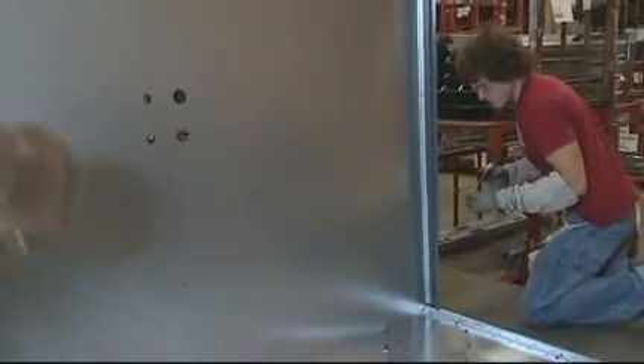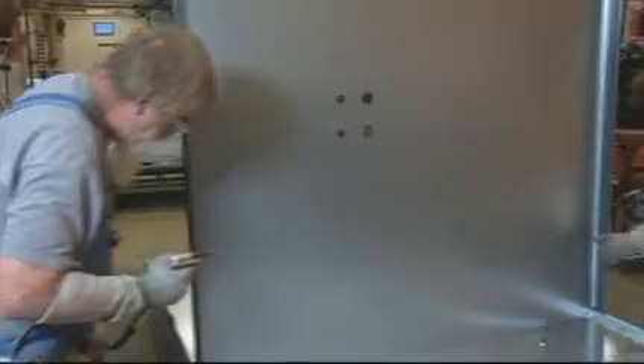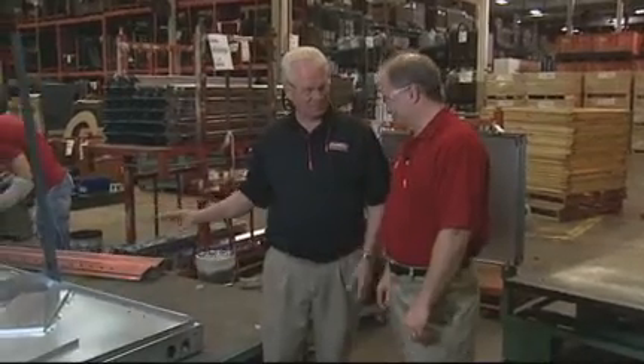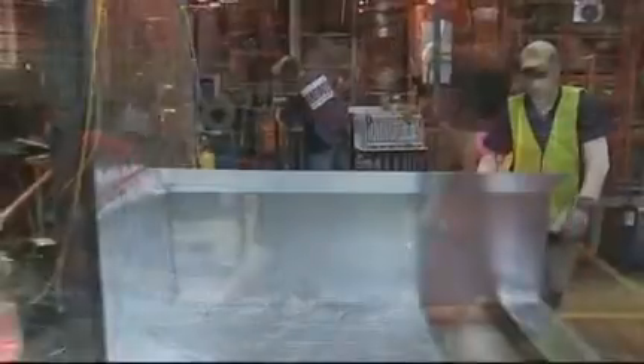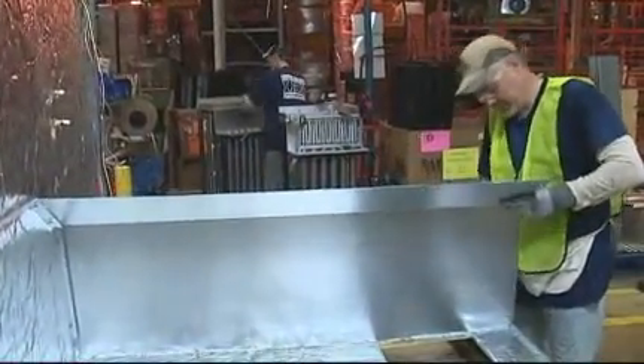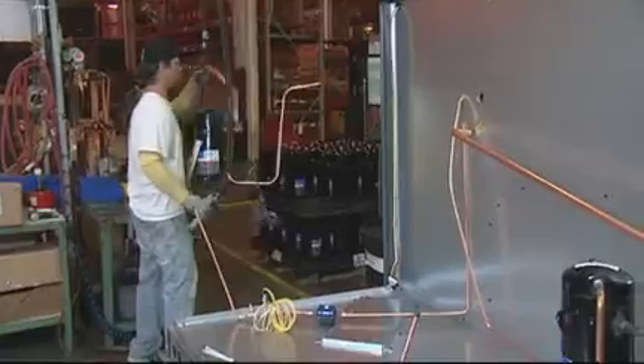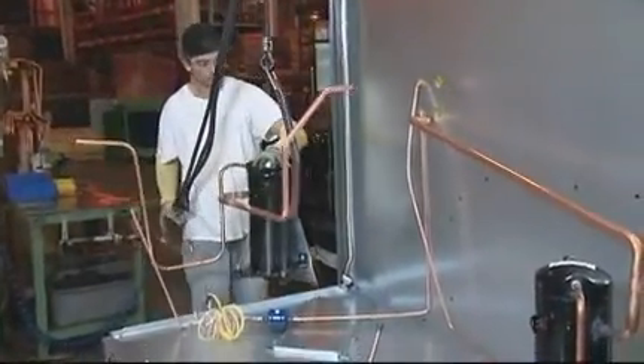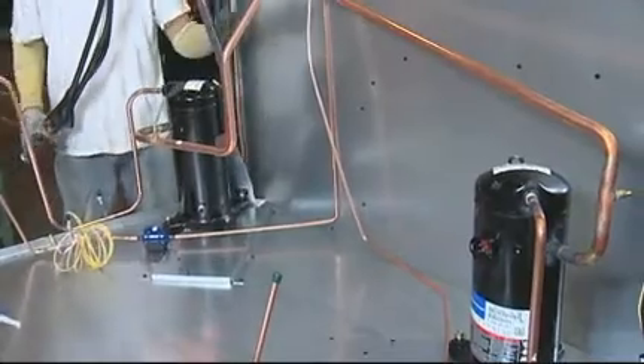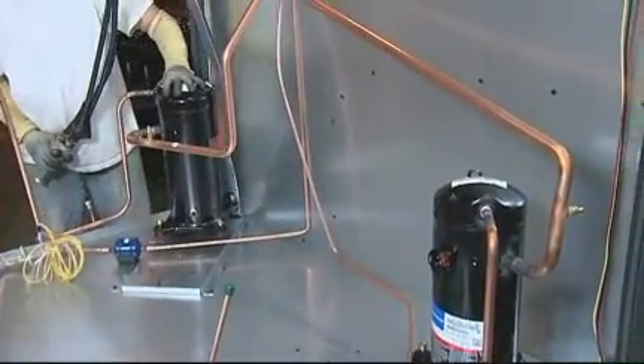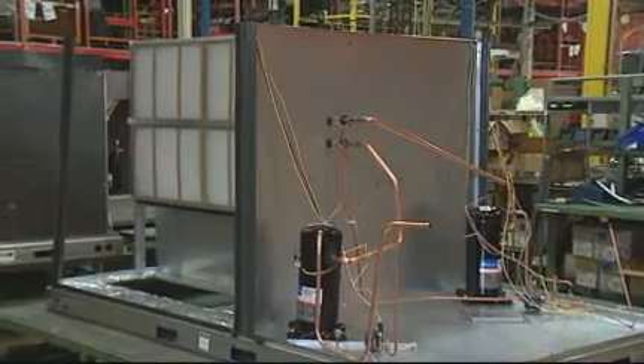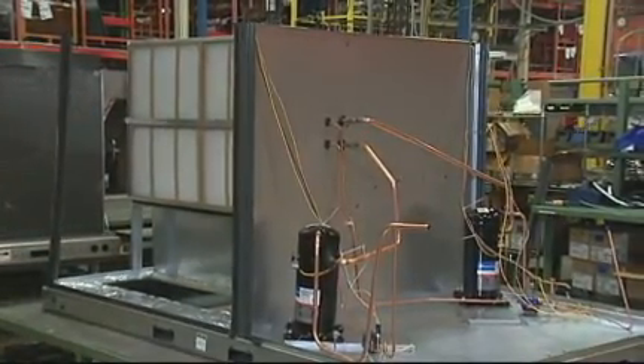This chassis runs 7.5 to 12.5 tons. Again, some of the same concepts and principles that went into the design of the smaller product I mentioned, same thing. Designed the footprint to match existing curbs. All of our 7.5 and higher have 2 refrigerant systems. Customers told us it's very important in a commercial application that if they have anything wrong with a unit, if just one side goes down and they still have some cooling, they can keep their business running. Sure. We listen to our customer, and every design unit 7.5 and up has 2 equal size systems so that it can always be in operation.